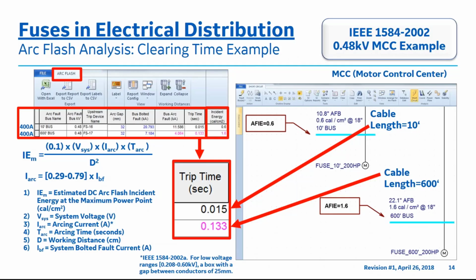The 600-foot cable, with the arcing current trip time, noted as the arcing time, or T-arc, has more influence on the arc flash incident energy label from the arc flash analysis report, with a corresponding clearing time of 0.133 seconds, which reflects the higher arc flash label of 1.6 calories per centimeter squared, shown on the bottom right.